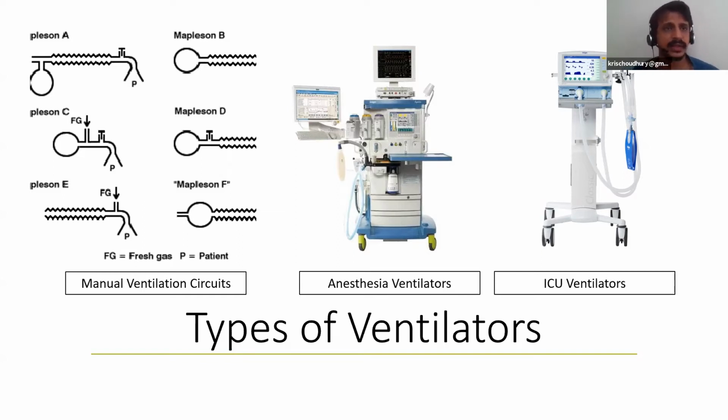So these ventilators basically even detect and understand how a patient is breathing, and try to mimic their breath, and try to ensure that a patient can be weaned off a ventilator. A lot of patients would be in a coma, and they would take time. First they take ventilator support, and slowly they have to be removed from the ventilator. So it's only the ICU ventilator that is capable of that kind of functionality.